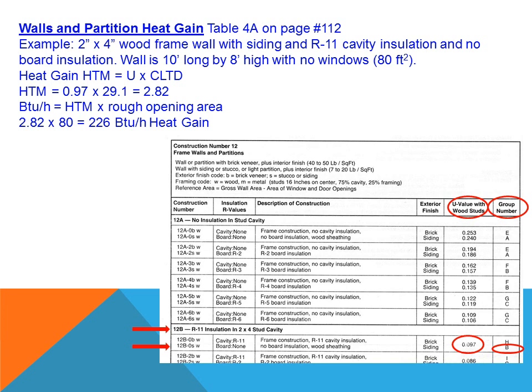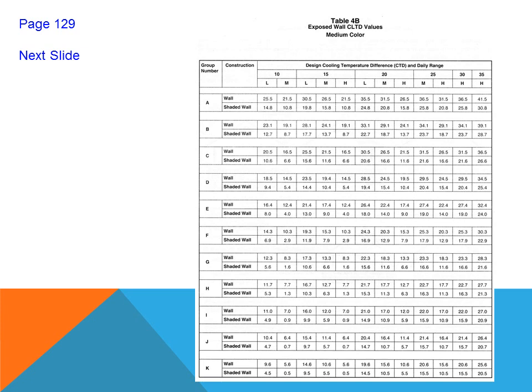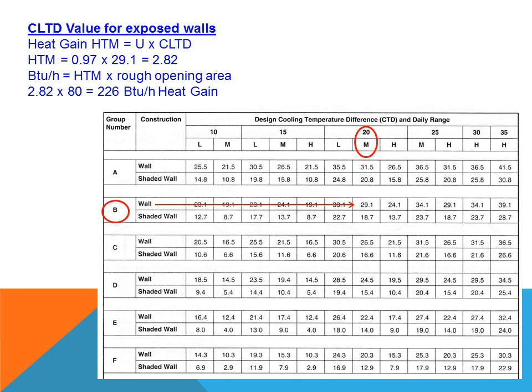To show how this works: we go through the different columns, look at the construction number — it's a good thing to record those numbers because you'll be going from table to table and chart to chart. For example, with R11 insulation in a 2x4 stud construction, either a brick or siding type exterior finish will give us a certain heat transfer multiplier or U-value. Be sure to also use the group number information. For exposed walls using cooling values and a medium color, we can see that the multipliers change somewhat based on the color of the exterior sheeting.